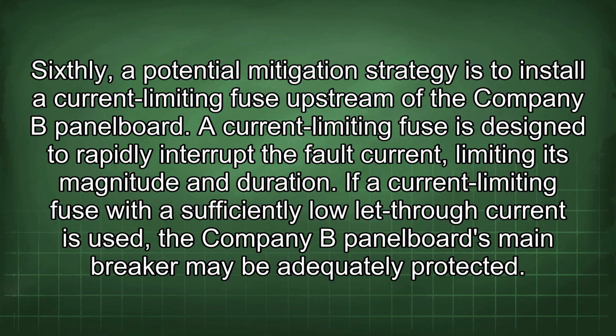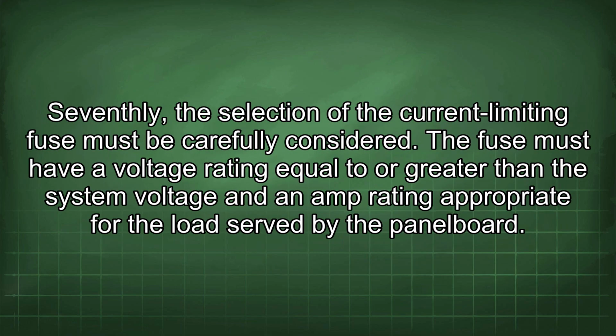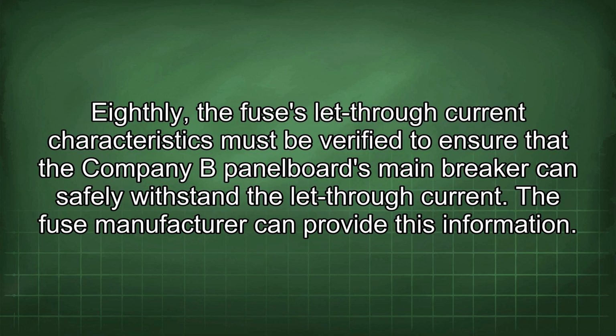If a current limiting fuse with a sufficiently low let-through current is used, the company B panel board's main breaker may be adequately protected. Seventhly, the selection of the current limiting fuse must be carefully considered. The fuse must have a voltage rating equal to or greater than the system voltage and an amp rating appropriate for the load served by the panel board. Eighthly, the fuse's let-through current characteristics must be verified to ensure that the company B panel board's main breaker can safely withstand the let-through current. The fuse manufacturer can provide this information.